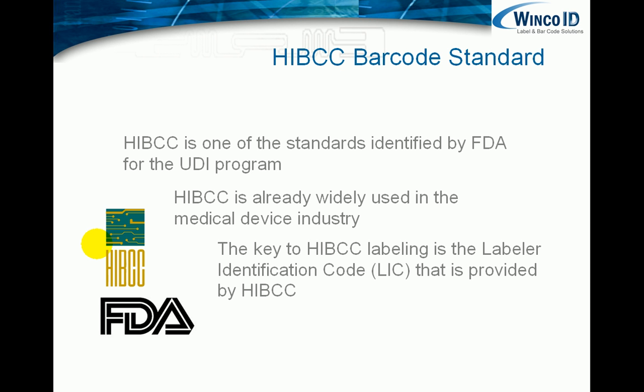The key to HIBCC labeling is what's known as the Labeler Identification Code, the LIC, that is provided by HIBCC, rather like the GS1 company prefix comes from GS1 if you're using GS1 barcodes.